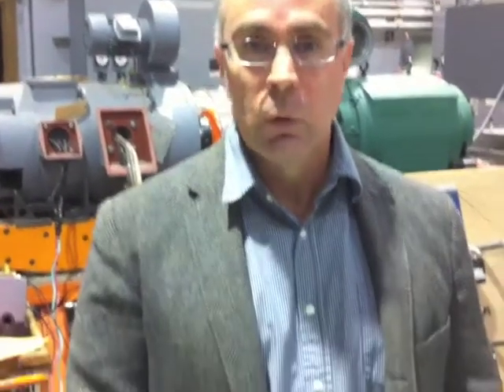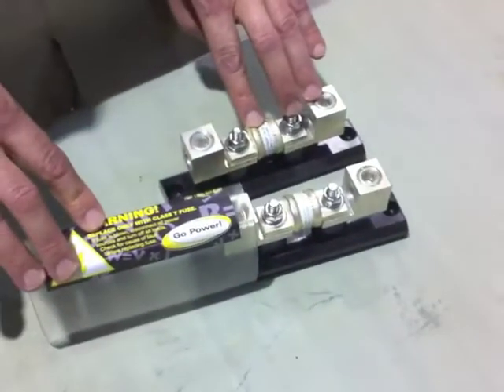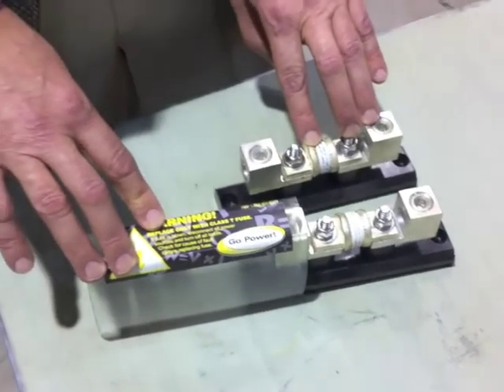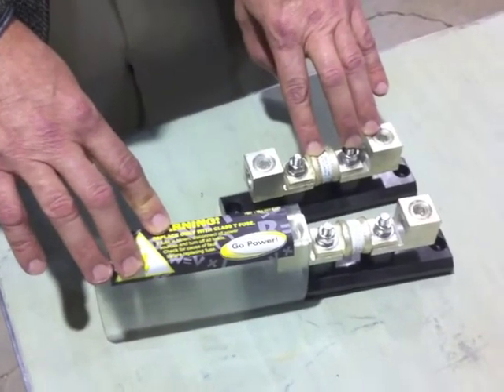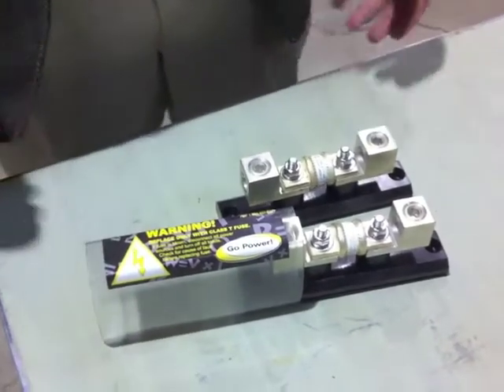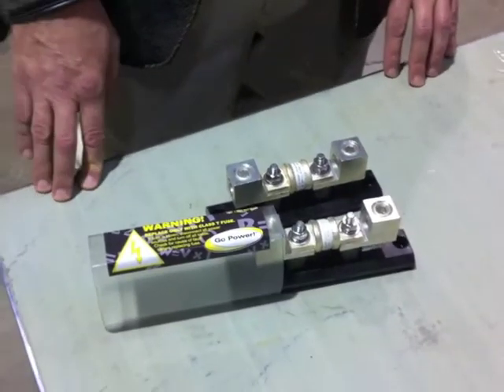The core of the battery simulator was a 100 amp rectifier. However, for 50 kilowatt tests, a 200 amp rectifier would be more appropriate. So we are leaving next year's team two 200 amp fuses that can be used to protect that 200 amp rectifier. Also, next year's team needs to know that Wallace Lab limitations are 175 amps DC.